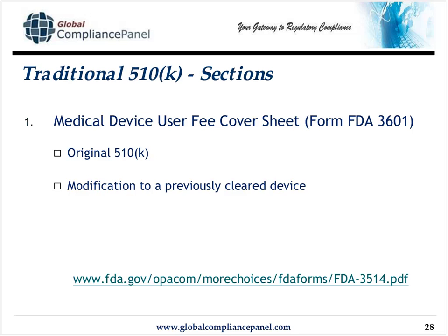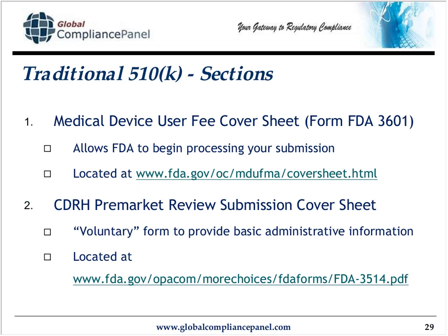Some of us use specials for our modification 510Ks, but you can use a traditional for a modification if you so decide. Section 1 is the user-fee cover sheet, and the FDA will not do anything without the user-fee cover sheet with your 510K. As I mentioned earlier, you're going to submit a copy with your check, but you're also going to submit a copy with your 510K.